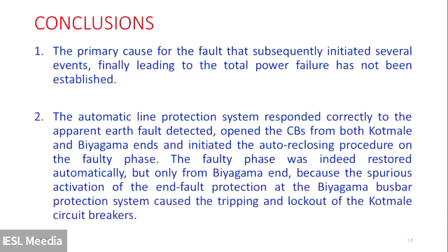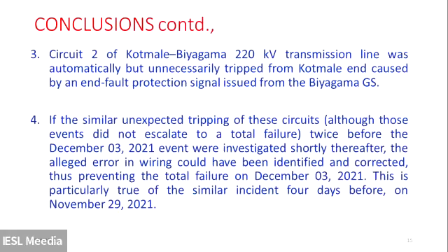Then the line protection operated correctly, that is, it was trying to reclose, but by the time it reclosed, the end-fault protection had operated with circuit breaker lockout. So you can't do anything beyond that point. So that is how the circuit 2 became unavailable.